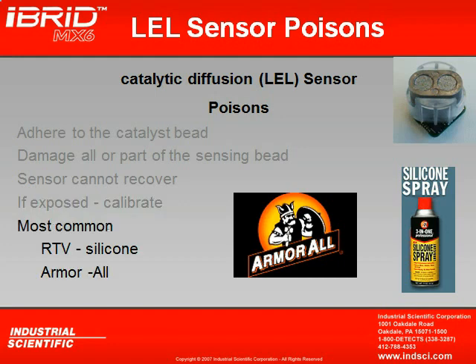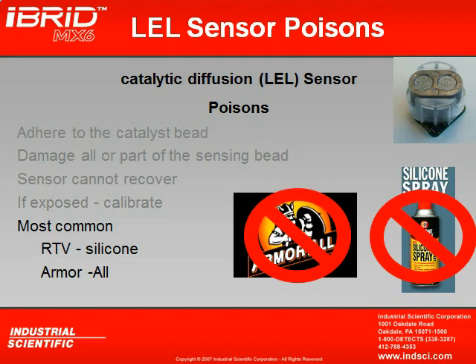And like we were saying, we have to avoid agents that have silicone in them, most notably Armor All. A lot of people like to Armor All the dashboard of their company vehicles. Then they let the instrument sit up there in the hot August sun. Meanwhile, all that silicone is off-gassing. Over time, that may have a poisoning effect on your sensors. So we want to avoid any type of silicone-based product. Although the combustible sensor can detect any and all combustible gases, it is important to note that if your combustible sensor is poisoned, it'll first lose its sensitivity to methane before any other combustible gas.